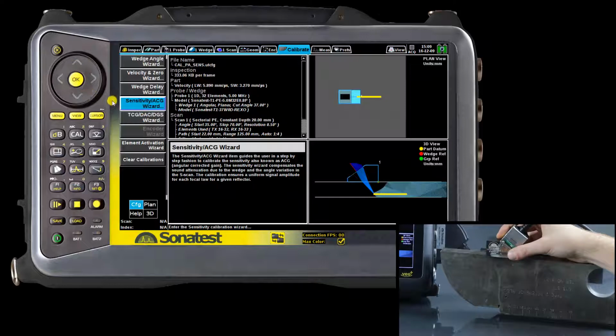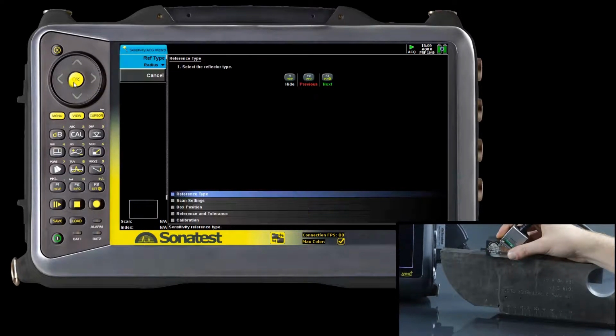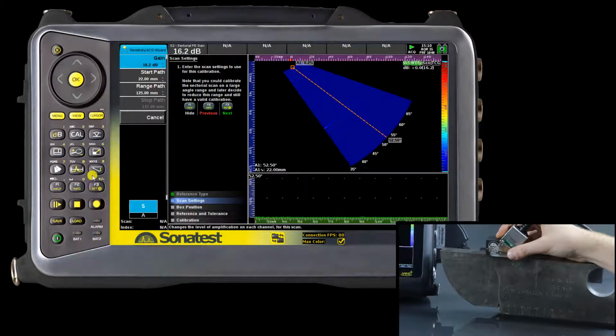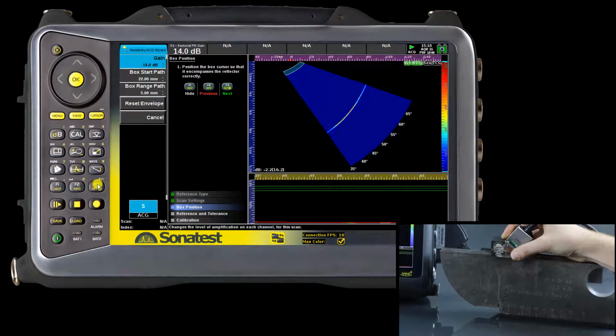We are still in the same setup as the previous calibration video, and we are going to select the sensitivity wizard. As a reference reflector, you can choose from 3 different kinds of geometry, either a radius, a thickness or a side drilled hole. For this calibration block, we will be using the radius geometry. To make the calibration easier, we suggest you put the signal amplitude slightly under the reference level. The next step is to set the extracting box dimensions, making sure that all the signal is within the box.